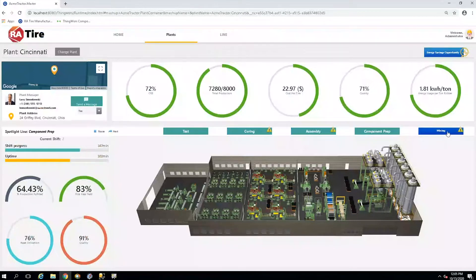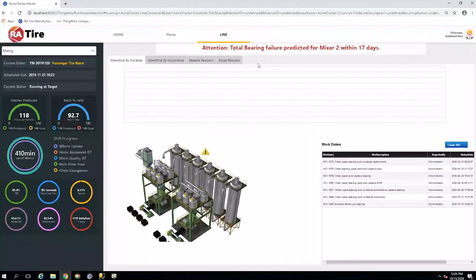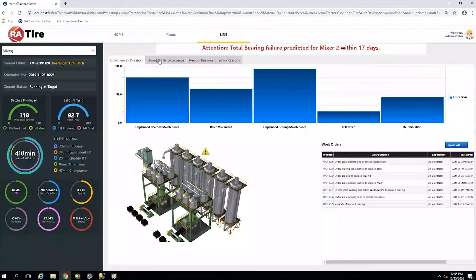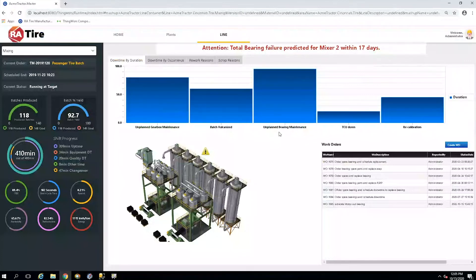So first we'll start with the mixing area. From the mixing area screen, we can see that availability is lagging. As we look across our downtime by duration and occurrence, it appears that there was some unplanned gearbox maintenance as well as some unplanned bearing maintenance. And we'll see an alert that says there's a total bearing failure predicted for Mixer 2 within 17 days.